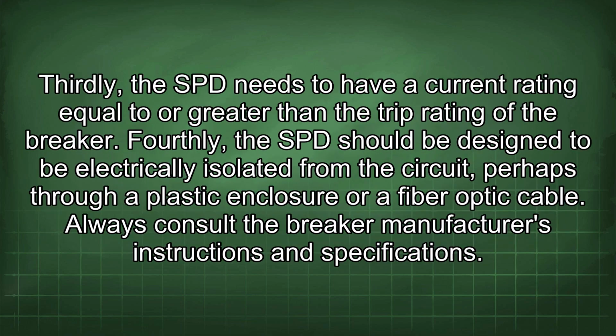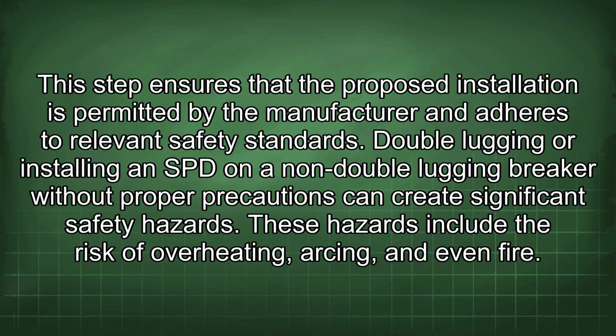Thirdly, the SPD needs to have a current rating equal to or greater than the trip rating of the breaker. Fourthly, the SPD should be designed to be electrically isolated from the circuit, perhaps through a plastic enclosure or fiber optic cable. Always consult the breaker manufacturer's instructions and specifications. This step ensures that the proposed installation is permitted by the manufacturer and adheres to relevant safety standards.